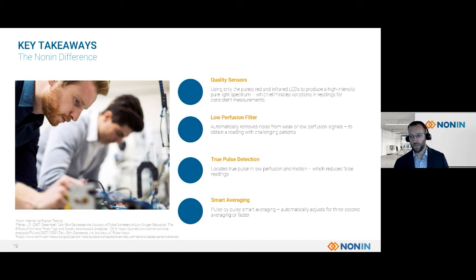PureSat technology also features true pulse detection, which reduces false readings, locating the true pulse in low perfusion and motion. So with motion, we're able to remove these artifacts, reducing the time it takes to get a reliable measurement. And what this means to you and the patient is reliable measurements that are consistent, trustworthy, and good quality. Nonin's PureSat technology is also equipped with pulse by pulse smart averaging. This is the fast averaging that is either 3 seconds or even faster. This saves time, as there are no modes to set, and intelligence automatically adjusts the averaging for challenging conditions. The combination of pure light and PureSat technologies provides a highly responsive, precise system for accurate and reliable readings, even under the most challenging conditions.